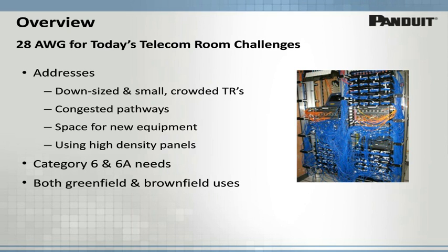So a key point here, and the reason that we're talking about telecom rooms and data centers for this cabling, is that the space within those two areas is prime real estate due to its function and the cabling equipment combined there. Yet as we can see in the picture, the copper patch cabling often drives how well we can meet the space challenges there. For example, we can see in the TR rack shown that while there is available rack space in the upper left for new equipment, there's little or no room to effectively add the patch cabling that would be needed. And this is a very common challenge.